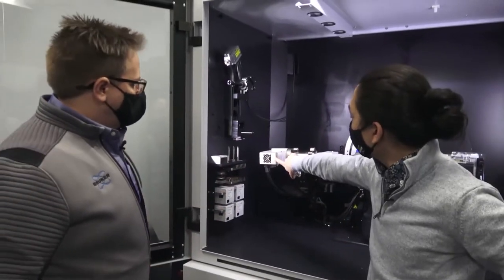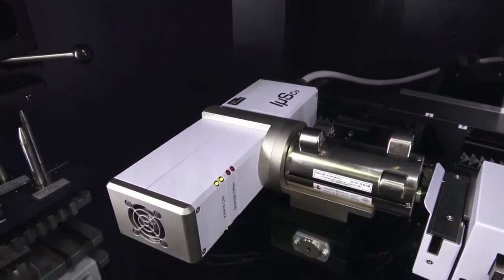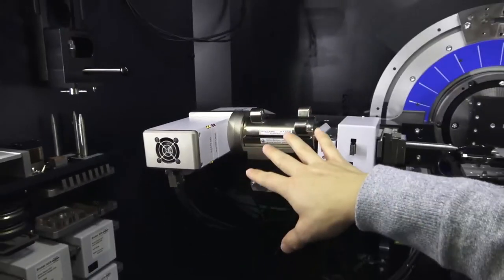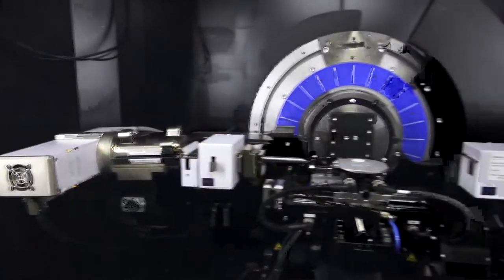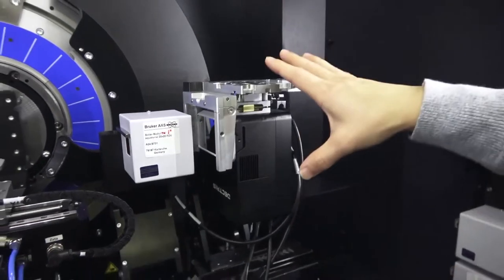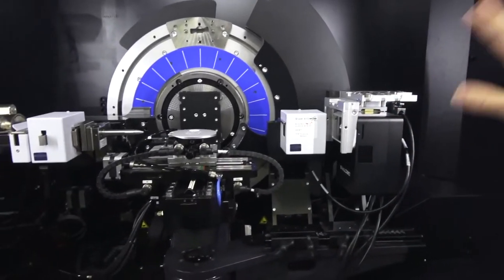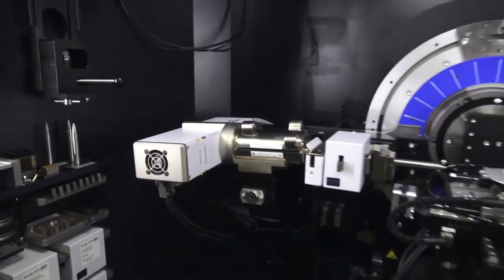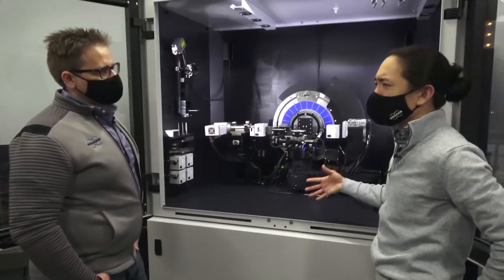And that's one reason you'll see there's a fan right here — this fan does all the cooling. What's really nice about this system is that there's no cooling water. We call this the IμS — the meaning for microfocus. The detector on this side is our EIGER detector — a very large multimode detector, 0D, 1D, 2D — and it's also air-cooled. You don't need any cooling water for this particular system, which is super convenient for areas where you don't have the infrastructure or you're trying to be more environmentally conscious.